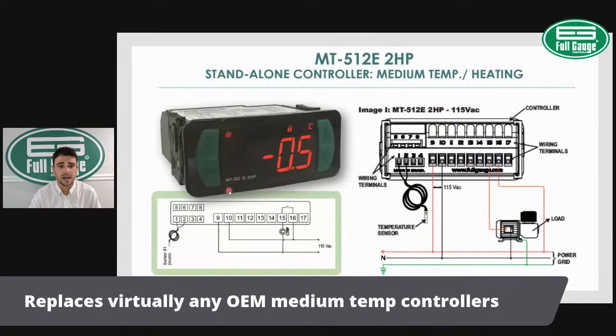So as I mentioned, the 512, it's a dual voltage product. So you can actually power the 512 on the terminal 9 and 10 for 110, or terminal 9 and 11 for 220. One nice feature about this controller is that we have an independent circuit for the relays. So what that means, having an independent circuit for relays.